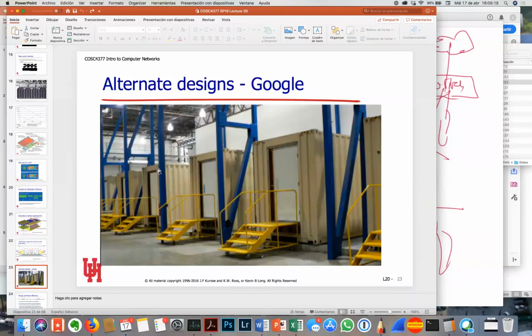They're all the same. So if you lose a few in here, you're taking the redundancy approach instead of the reliability approach. You will not go inside and try to fix it or replace it. Once a third of them have died, or you've got newer systems that can save enough power that it's worth reinvesting, the claw will come and pick up this container and replace it with another one that's got newer, faster, cheaper, cooler equipment. You just do this Lego block by Lego block, but each one of them has 3,000, 4,000, 5,000 servers inside. And you have hundreds of thousands of these around the planet.